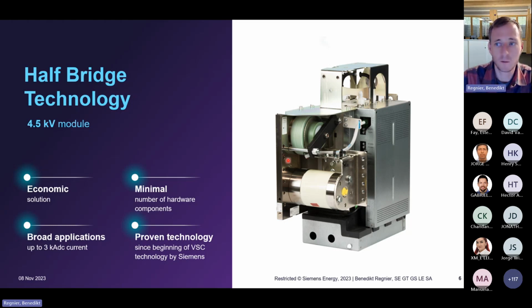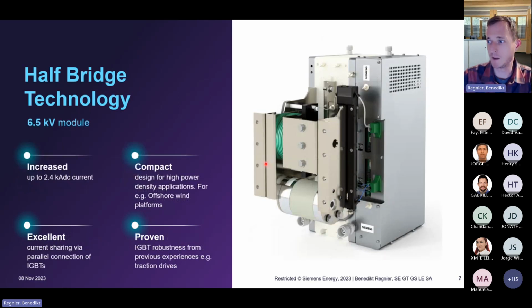And the second module, which we have in operation or in execution, is our 6.5 kV module. That means the blocking voltage is higher in that module. The consequence is, for example, for a 500 kV solution, we need fewer modules. This can be interesting if losses are a very big topic, or if we need to build more compact and reduce some space here and there, then this solution is a good choice.